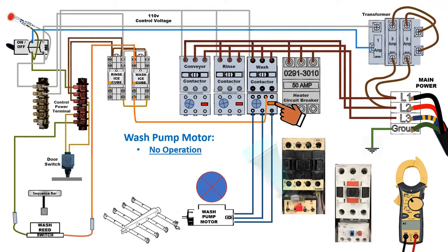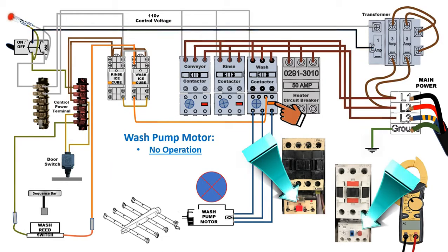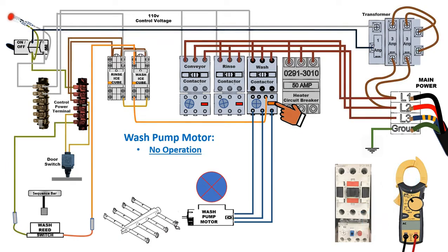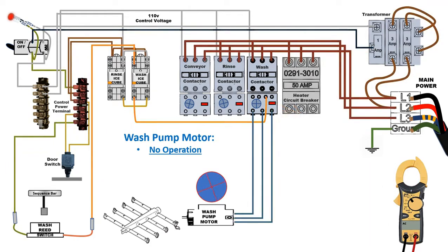Here are a couple of contactors. They come in different sizes and shapes. And here we're showing where the overloads are and where the reset buttons are located. We're going to push the reset button in to see if that energizes our wash motor. And as we're seeing, the overload was tripped. This allowed the wash motor to start working.